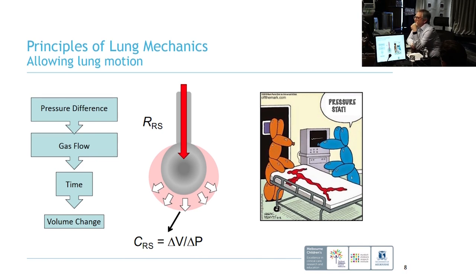We need to make sure that pressure difference is given over enough time to cause the lung to move, or enough time to allow the lung to deflate. It's through that pressure difference, with a flow of gas and adequate time, that you actually get tidal volume to change. The pressure difference needs to be big enough to overcome the forces stopping the lung from moving, because the lung wants to stay deflated. That's its natural state, like a big spring.